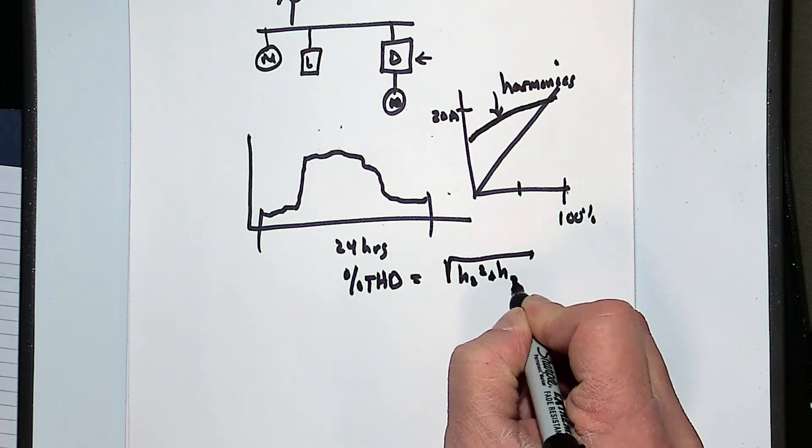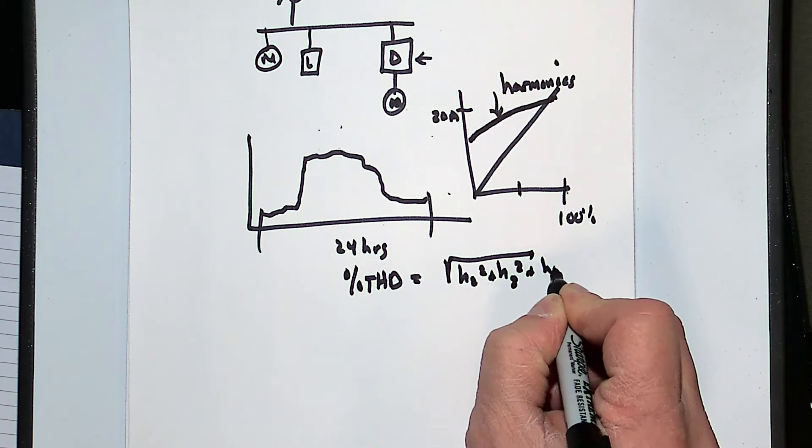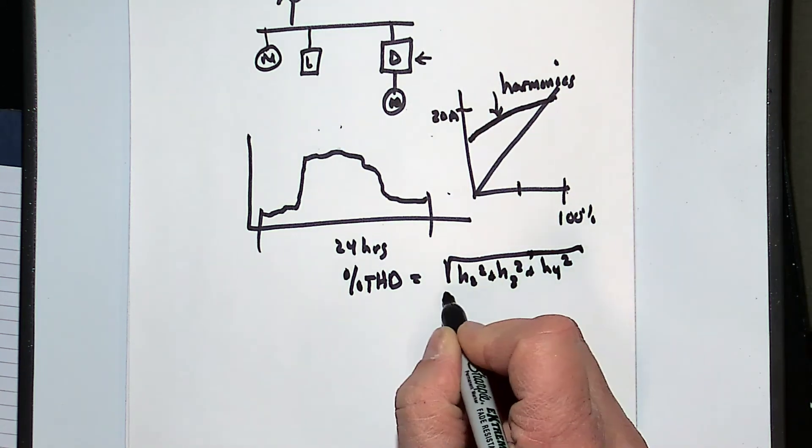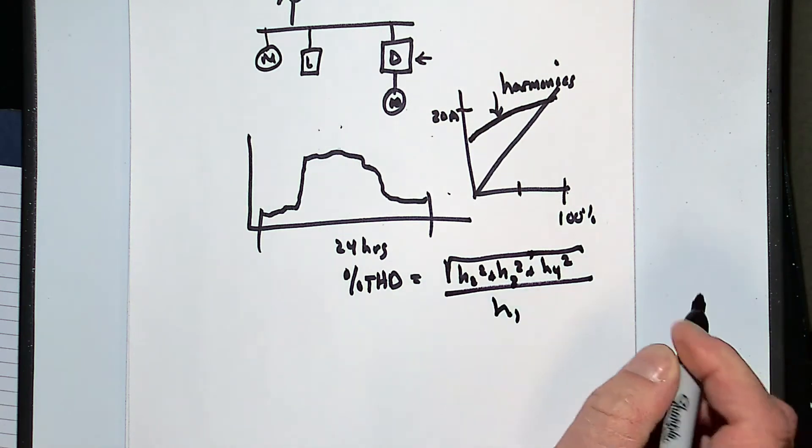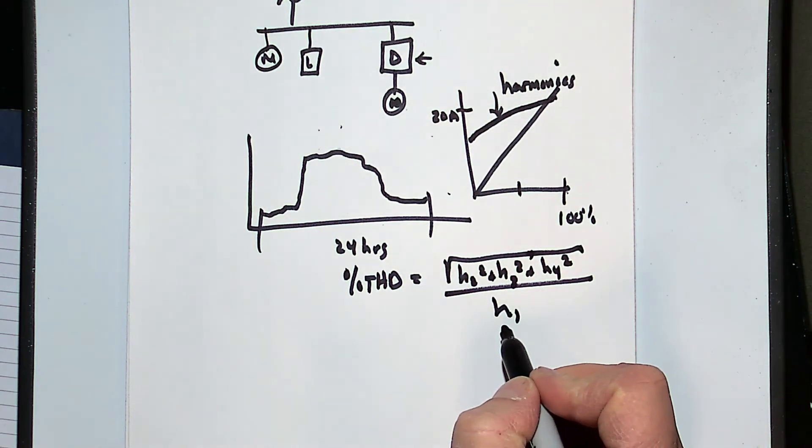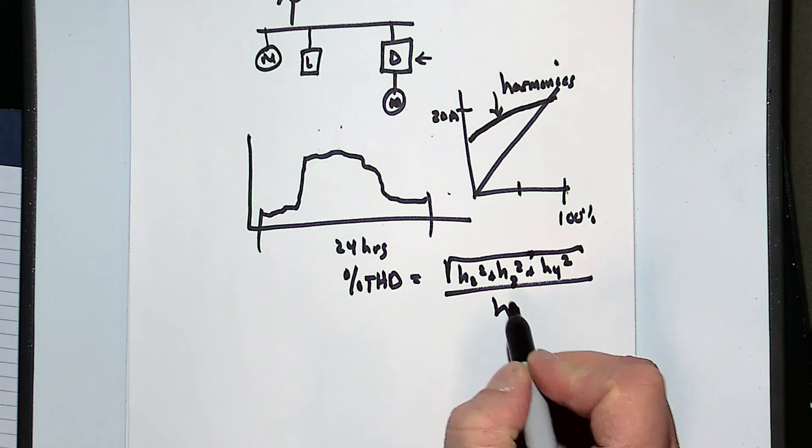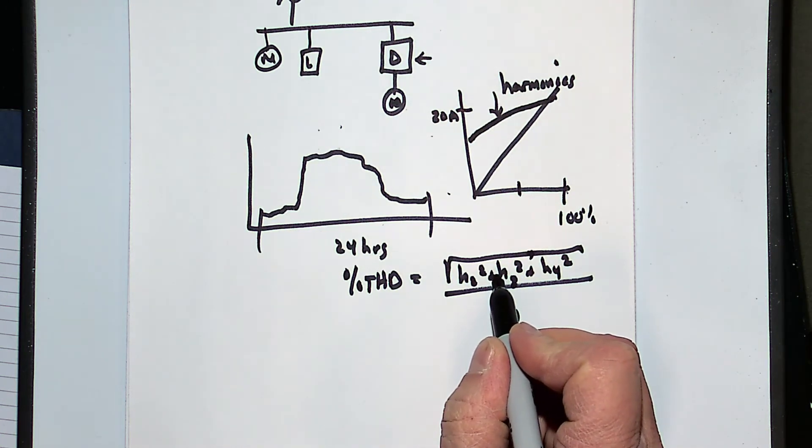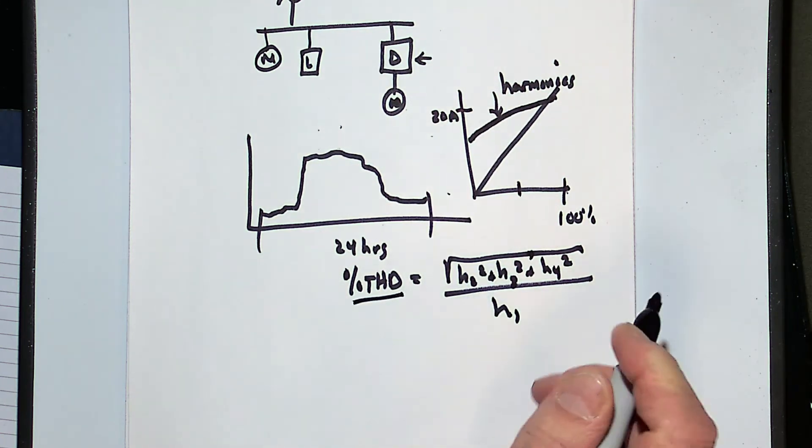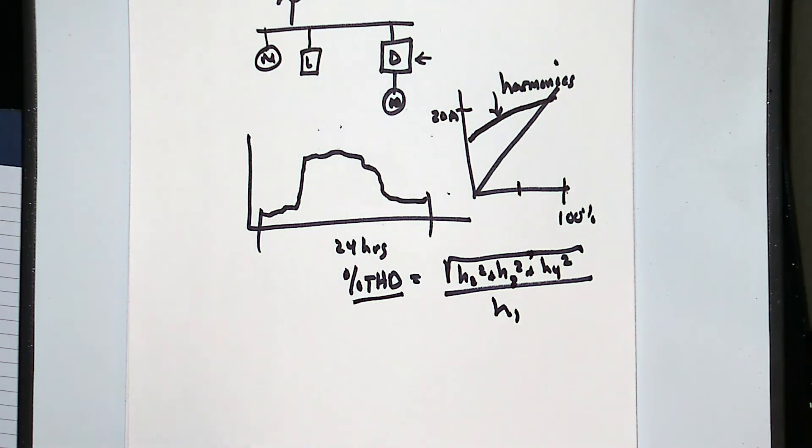H2 squared plus H3 squared plus H4 squared, and so on, divided by the fundamental. Because the fundamental changes linearly and the harmonics do not change linearly, my percent THD overnight and in times of light load will become a much bigger number.